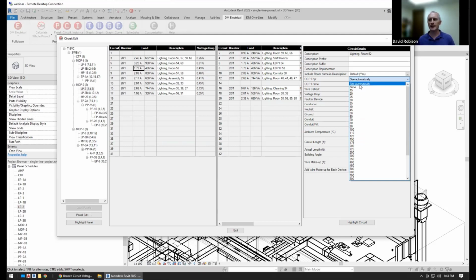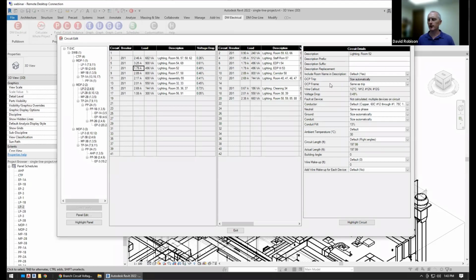When sizing automatically, it's going to take a look at the instance and the family settings and determine the overcurrent protection size based on that. So we're not going to take a look at those settings. That's going to be another training where we look at the instance edit and the family edit command, but we have lots of different places in the instance and in the family where you can control that. If nothing is set there, by default, we're going to do the breaker to be 125% of the connected load. And that handles 80% of your circuits.